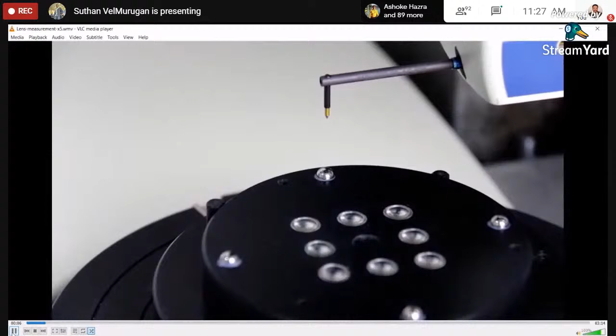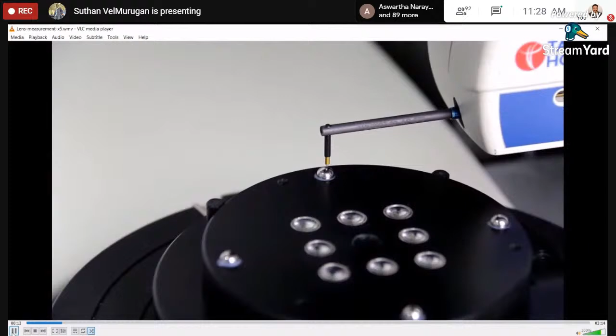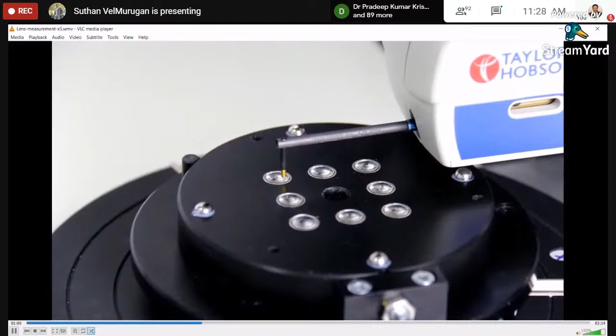So this is the contact profiler. The stylus tip, as I said, is made of a diamond material, and we have multiple small lenses. We can measure them all in a single setup. That is called a matrix. You can have n number of samples within the measuring volume of the machine, depending on the size of the sample. So in this example, we have about 8 samples. You can measure the 8 in a single setup, and we can have the error map of each of the 8 samples in a single page report.